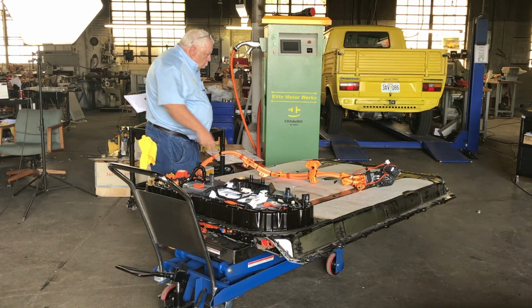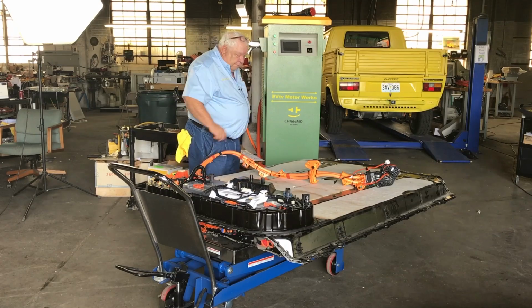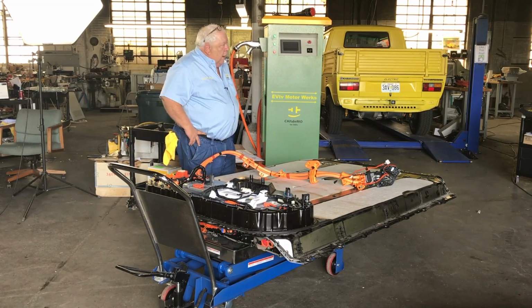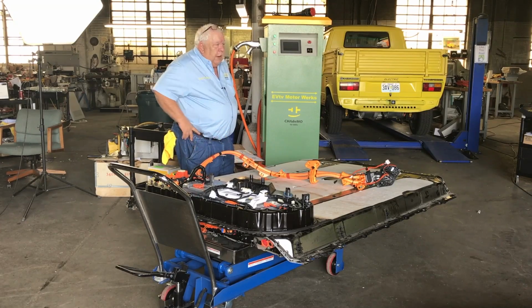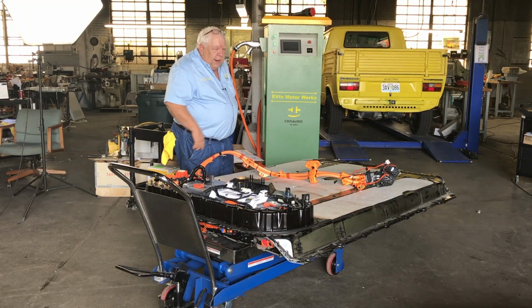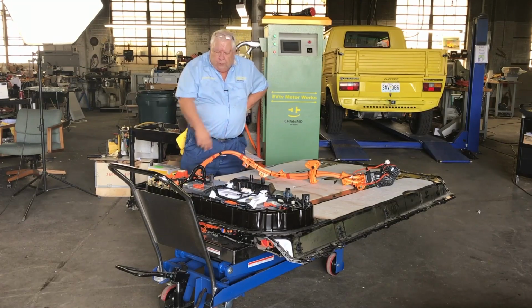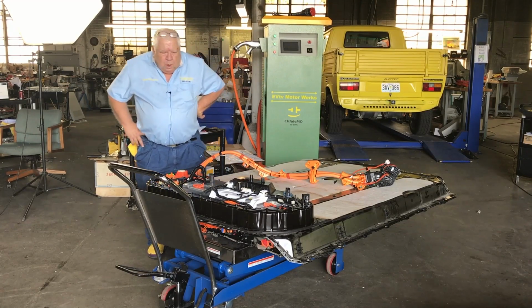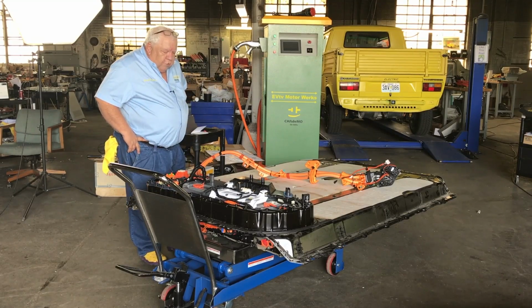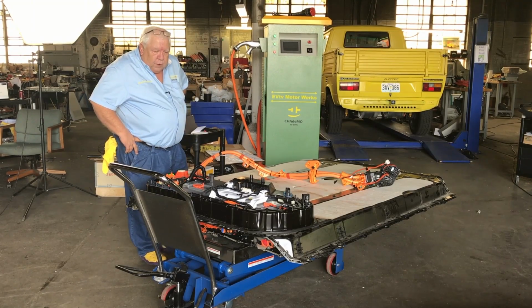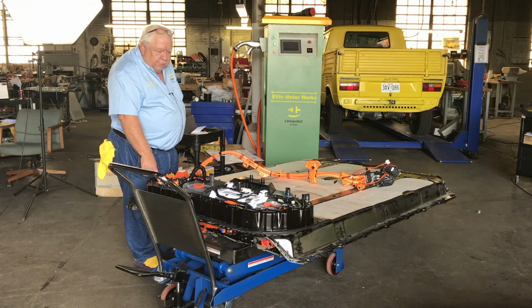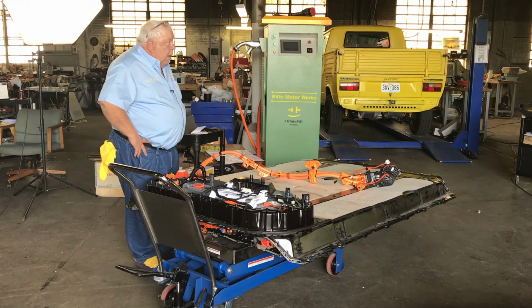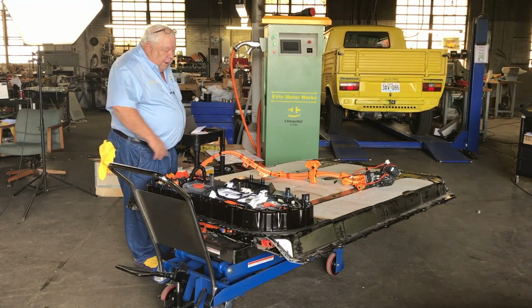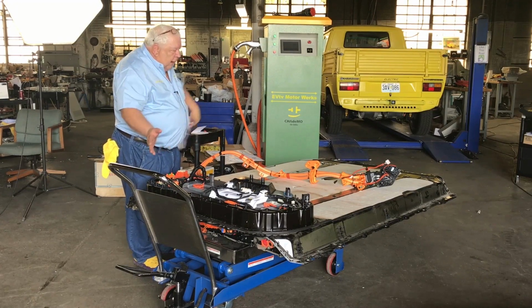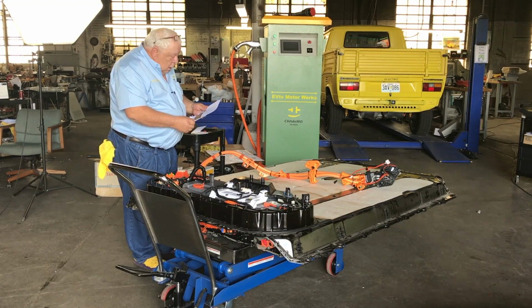It's arranged in 4 modules, not 16, and they're not even identical. One has 23 cells in it, the next one has 25, then 23, then 25. So you have 2 pairs. We've actually found live terminals under rubber booties here where we can measure the full battery pack voltage, and even a center tap voltage where we can measure between the 2 pairs of modules.